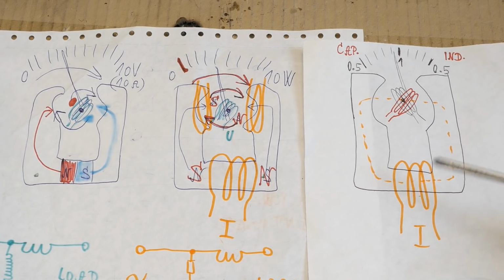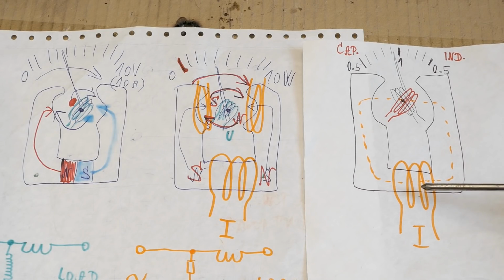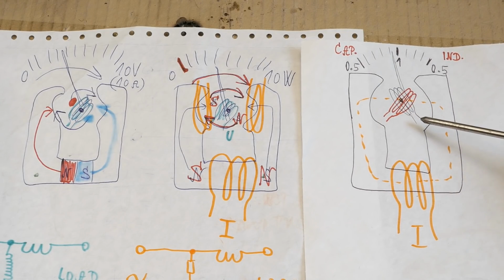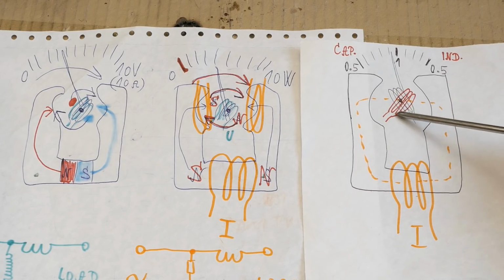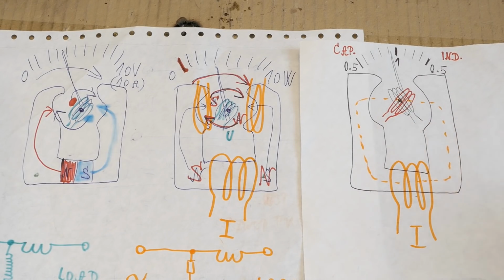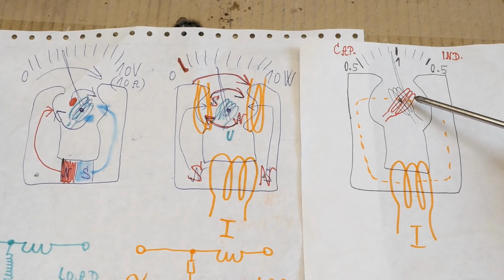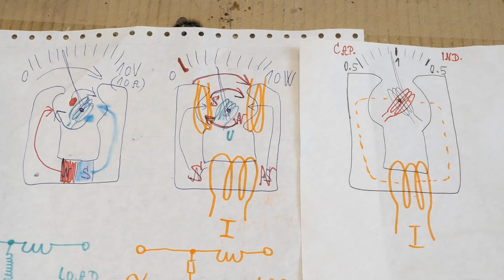It still has the current sensing coil, but instead of one voltage coil, it has two voltage coils moving in the magnetic field, and each of them is at a different angle. And each of the voltage coils is connected to an AC voltage with a different phase. Usually one of them is connected to a voltage which is ahead of the voltage of the phase you're sensing, and one of them has a voltage on it which is behind the voltage of the phase you're sensing. So basically one of them has a capacitive current in it and one of them an inductive current.